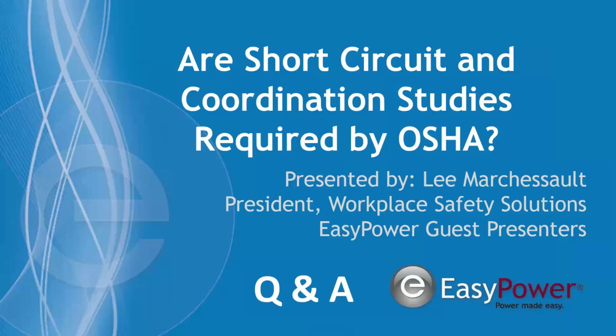Right. One last question: does adding a disconnect switch with a Class J fuse to an overdutied equipment controller solve it? It probably could, but I don't know if you would be coordinated with the system, and that might be the problem. It may be too fast for some of the breakers. So you're bringing down the arc flash level, but you may no longer be coordinated with the system downstream. So you have to look at that and play around with it to see if you can coordinate it.